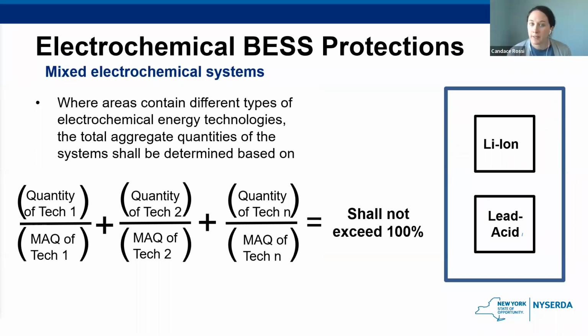So this is a requirement for mixed electrochemical systems in a single area. We'll see this when people use a different battery chemistry that are used for critical operating protection systems, maybe alarms or certain ventilations. These critical components should always work when the energy storage is completely shut down by a first responder or the battery management system. So basically, it's just a pretty simple formula to ensure that the total aggregate quantities of the systems are determined.